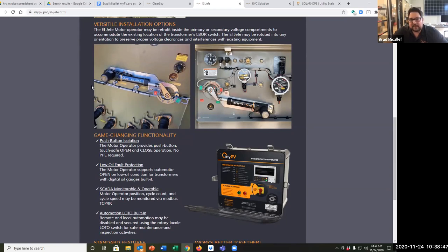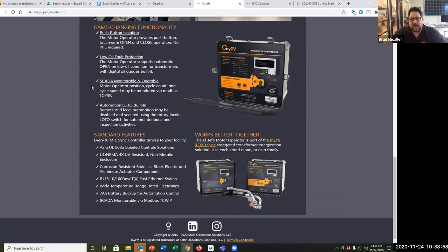And you start having to do really creative things. This is an example where in our territory, you might add a 5 or 10 megawatt project that has multiple step-up transformers, and after a storm, when all of those transformers would turn on all at once, they would actually create a power quality issue on the grid. So the utility set out to fix that. They basically said, is there a way to make the transformers turn on one at a time? There's a lot of different ways to solve this, but we were looking for a solution that could be both a retrofit and also have some ancillary benefits down the road too. So this motor operator product allows for the time delayed switching of transformers to reduce that inrush current.